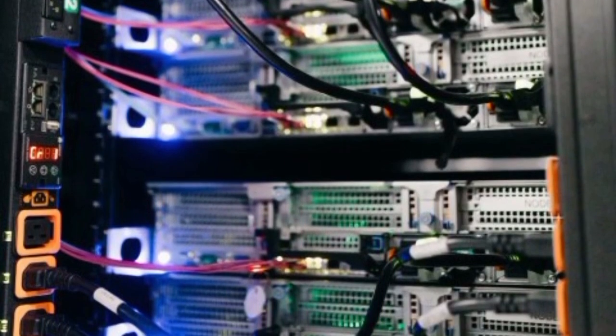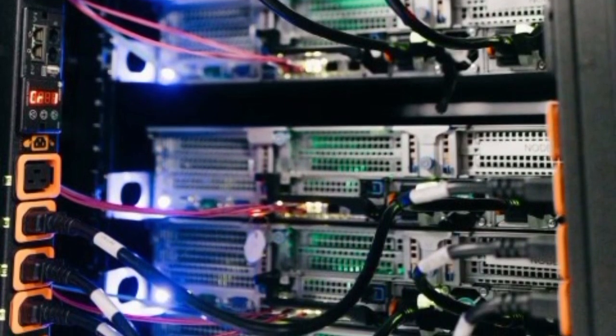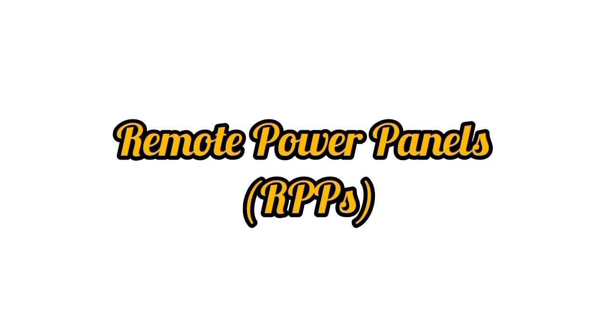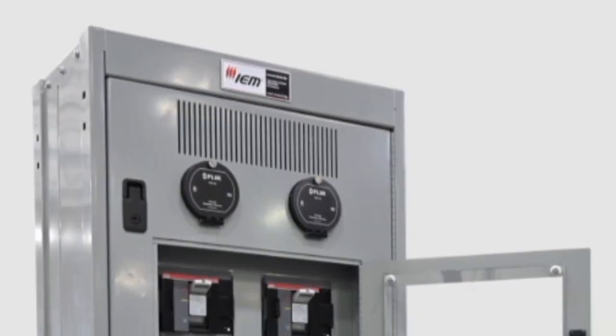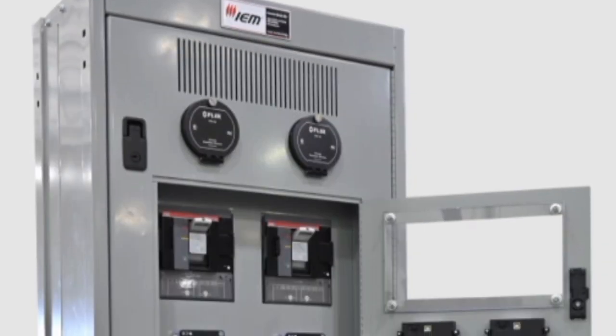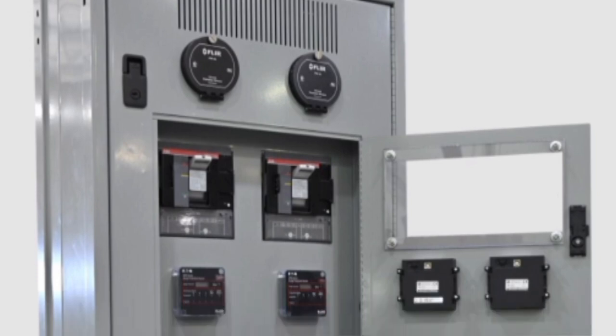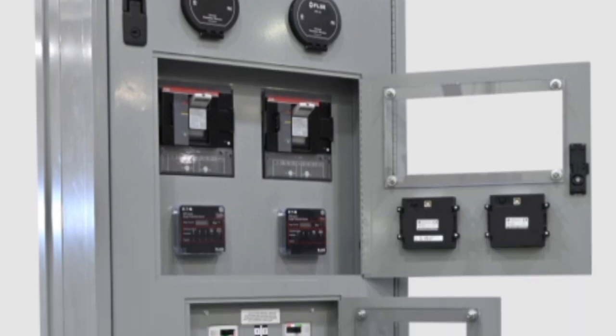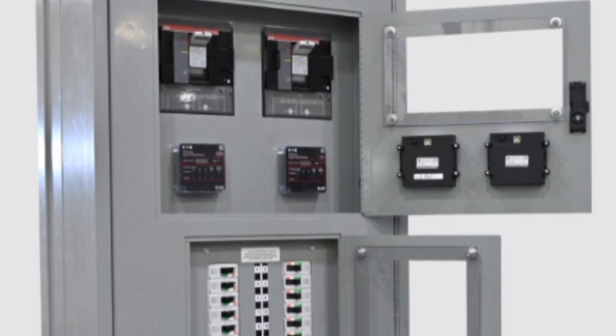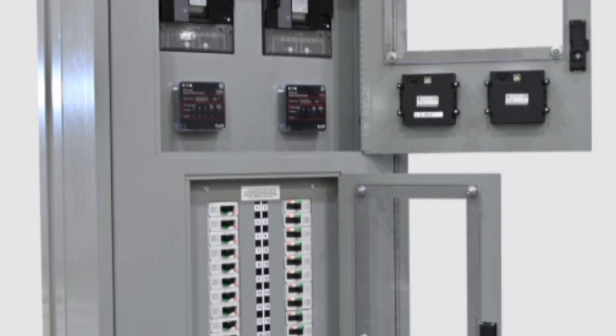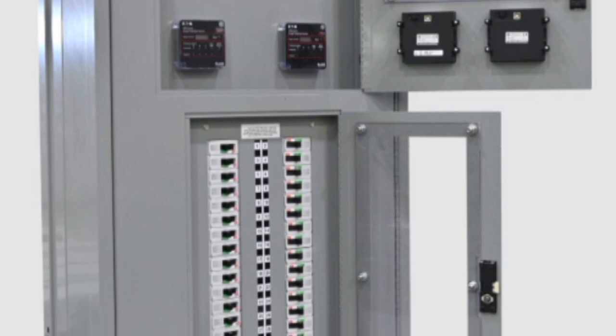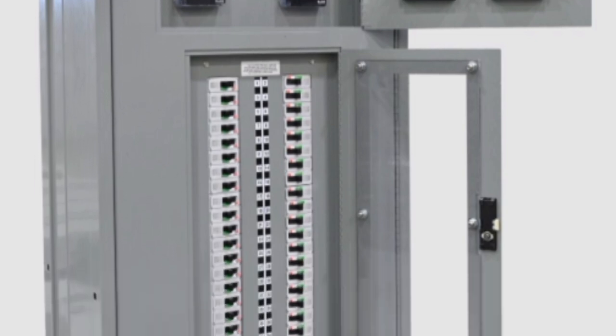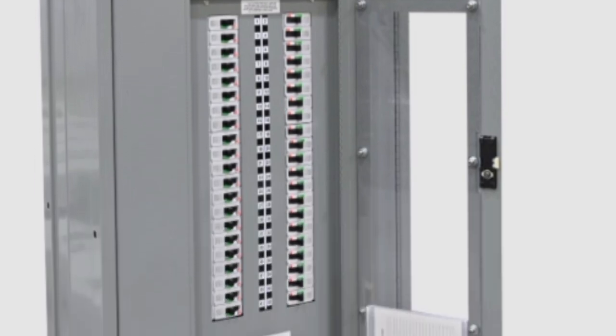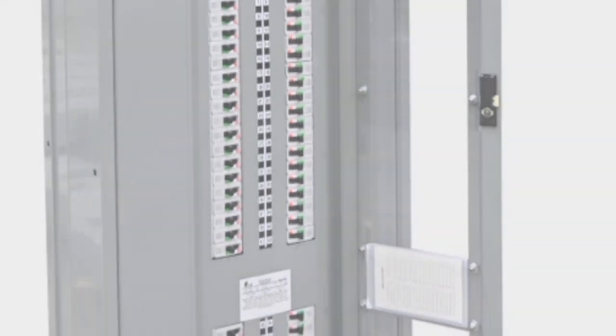They serve as the transition between facility-level distribution and rack-level distribution. Remote Power Panels, RPP. Remote power panels extend branch circuits deeper into the white space. They provide additional breaker capacity, flexible layout configuration, and scalability for future expansion. RPPs reduce the need to return to main distribution panels when expanding rack density.